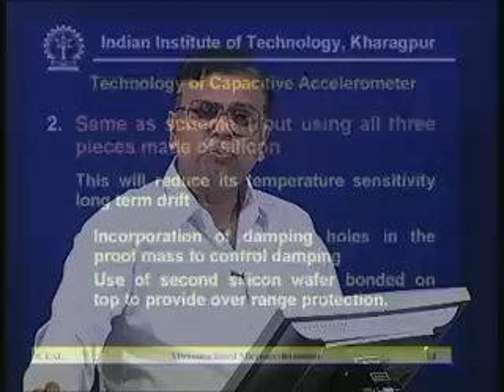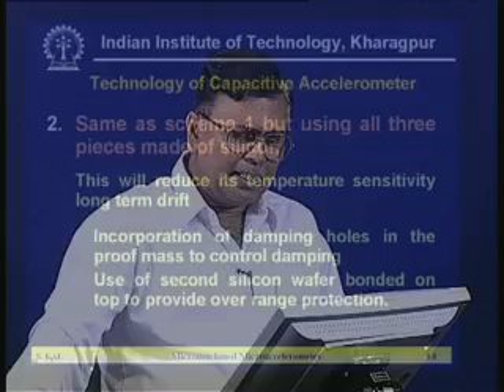So, this is important, and various kinds of damping technology are considered in the case of the accelerometer. In some cases, just the top and bottom cover plates are used and the ambient pressure inside is changed. Sometimes it is done in complete vacuum, and sometimes gas of different pressure and viscosity is used inside the encapsulation chamber. In some cases you can make perforations on the proof mass to get the desired damping factor. A second silicon wafer bonded on top provides over range protection.